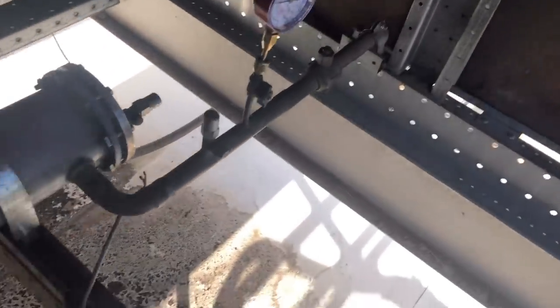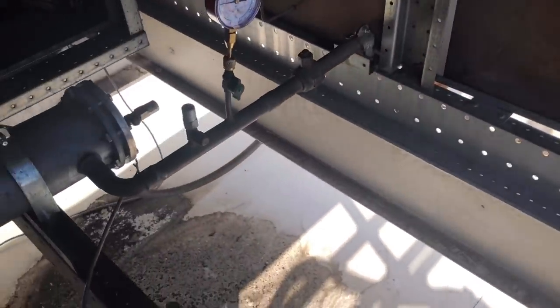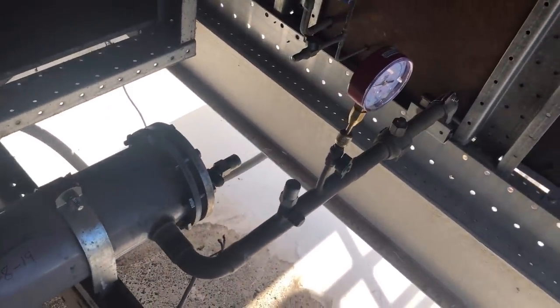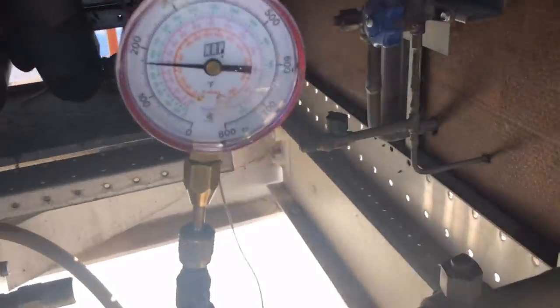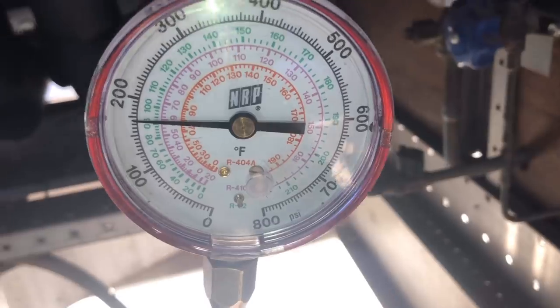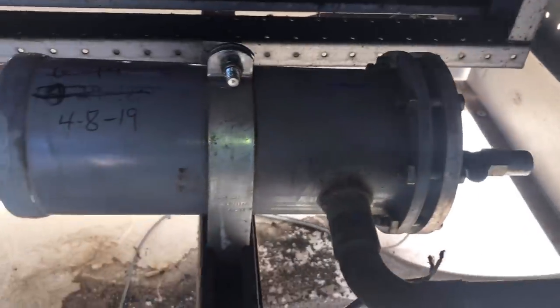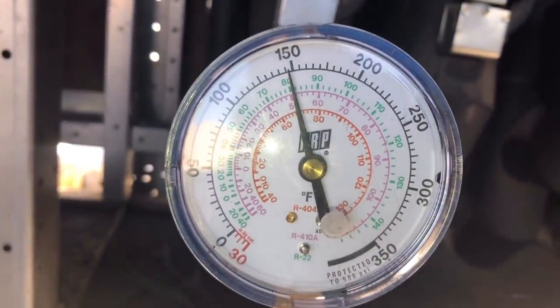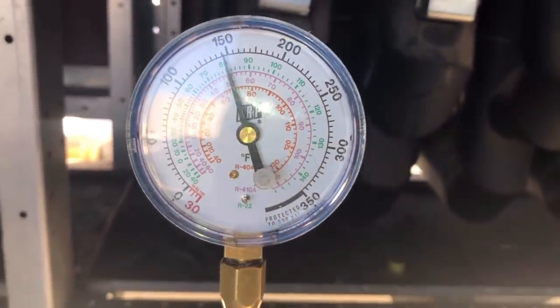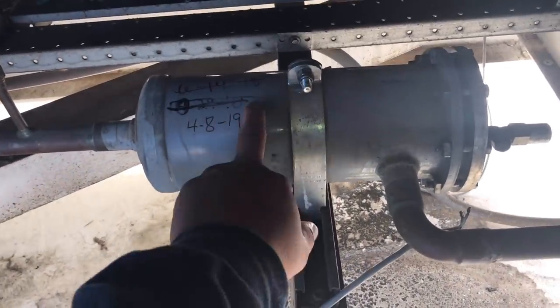We're here to check the dryers because the TXV screens have been getting plugged constantly. This is what we found: incoming pressure from the condenser is 170 PSI, then after the dryer it drops to 145 PSI — that's about a 25 PSI drop across these dryers. We're going to go ahead and change them out.